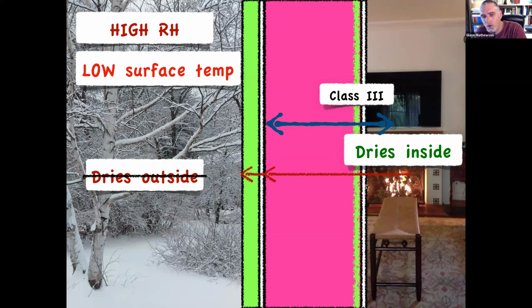Now we have increased the insulation bringing the heat to that condensing surface. So we're not going to get as much heat now coming to that condensing surface. But notice, we didn't change how rapidly the heat moves away from that condensing surface. And so what might happen now? We have a lower surface temperature there, and we're no longer above dew point temperature.